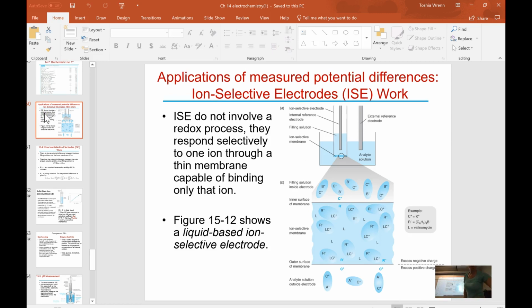We use this idea of measuring the potential difference between a standard electrode and a solution for a lot of our instruments. You've already encountered some of these, but they're the ion selective electrodes. You've used the calcium ion selective electrode, but you've also used the most common ion selective electrode, which is the one that is selective for the hydrogen ion, which is the pH probe. And the idea of how these ion selective probes work is based on these measuring the electrical potential from a standard half cell that's contained within the electrode, sheltered from the electrode from a very thin glass membrane.